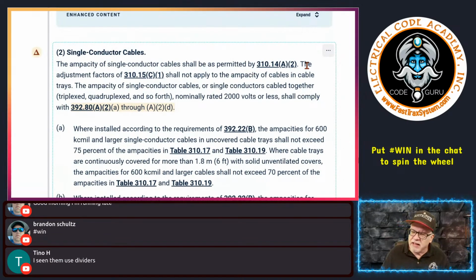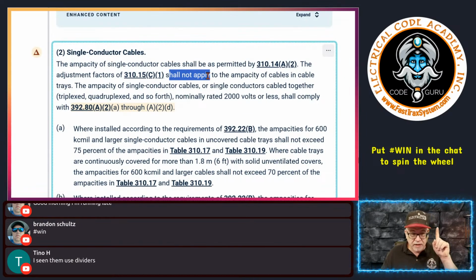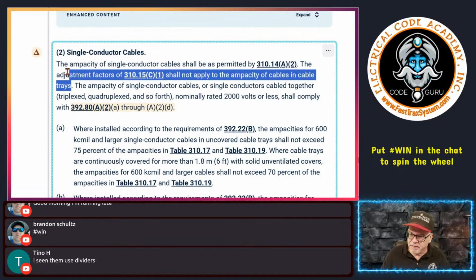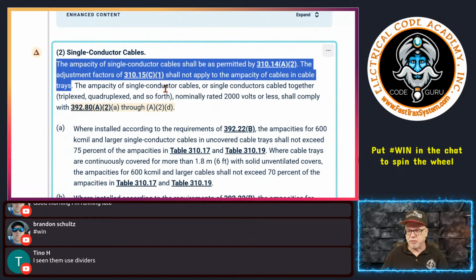It says the adjustment factors in 310.15(C)(1) shall not apply. Important stuff here. We're talking about single conductor cables and single insulated conductors. Shall not apply to the ampacity of cables in cable trays, okay? That's the first part, cables in cable trays.